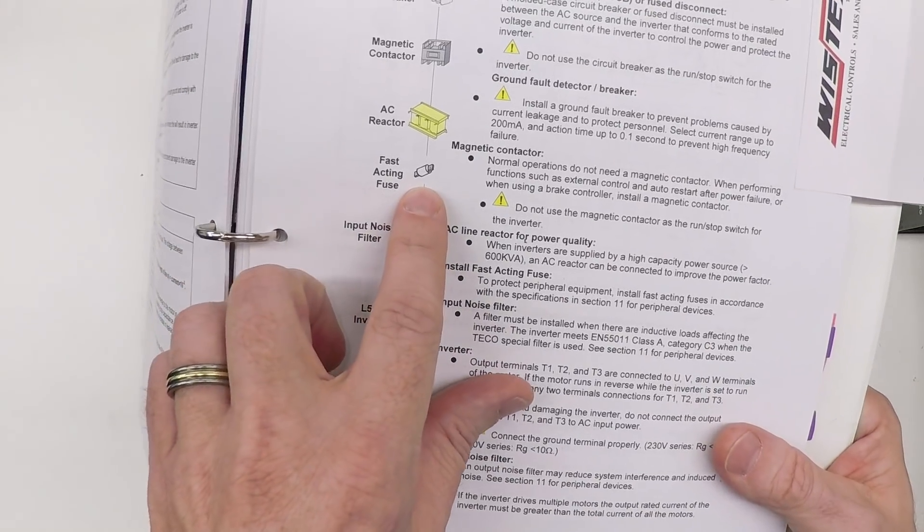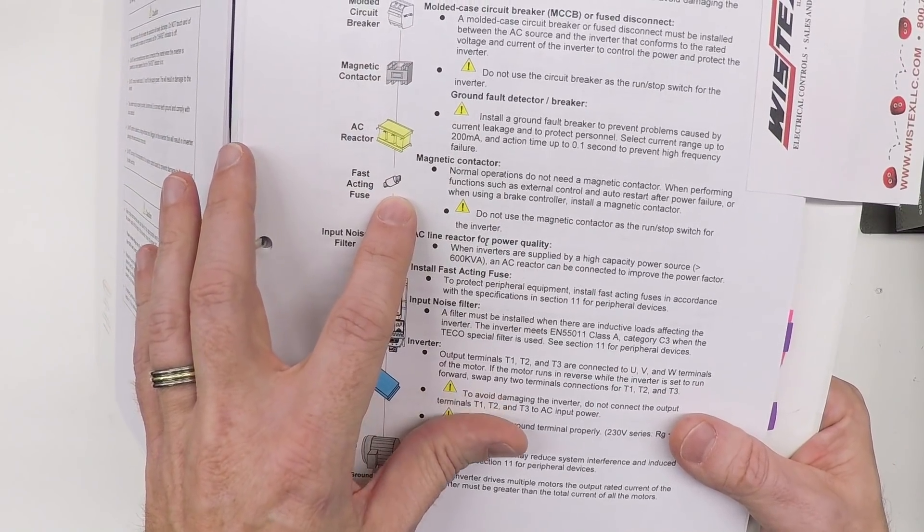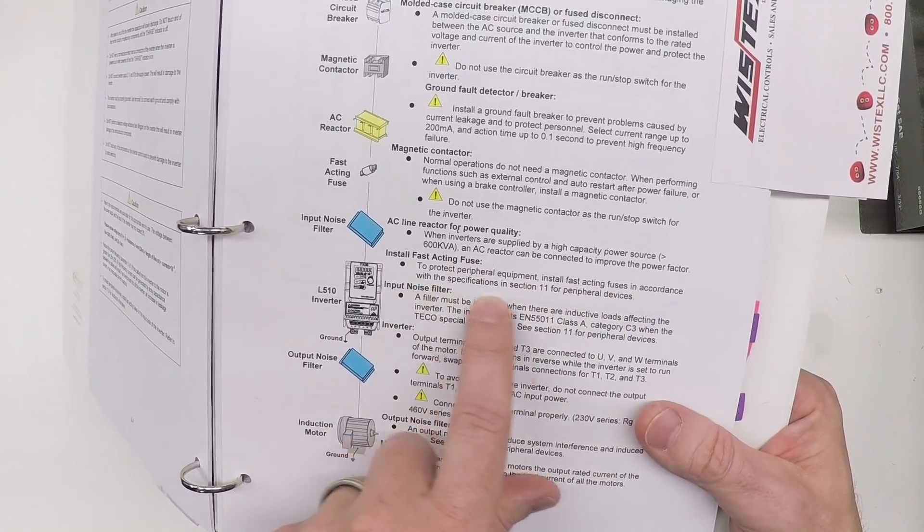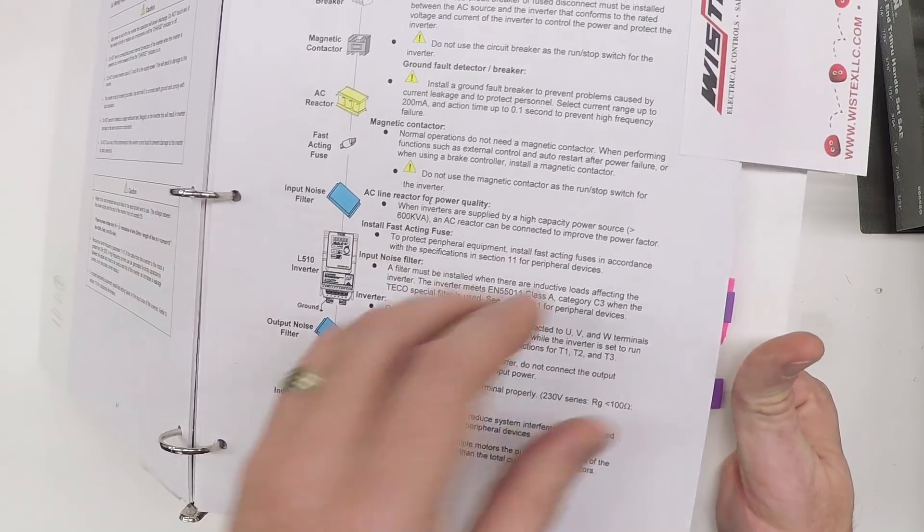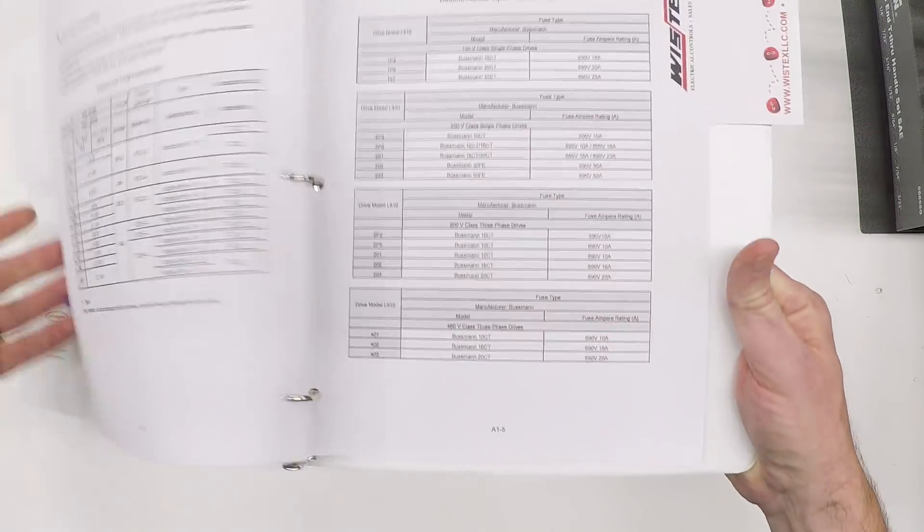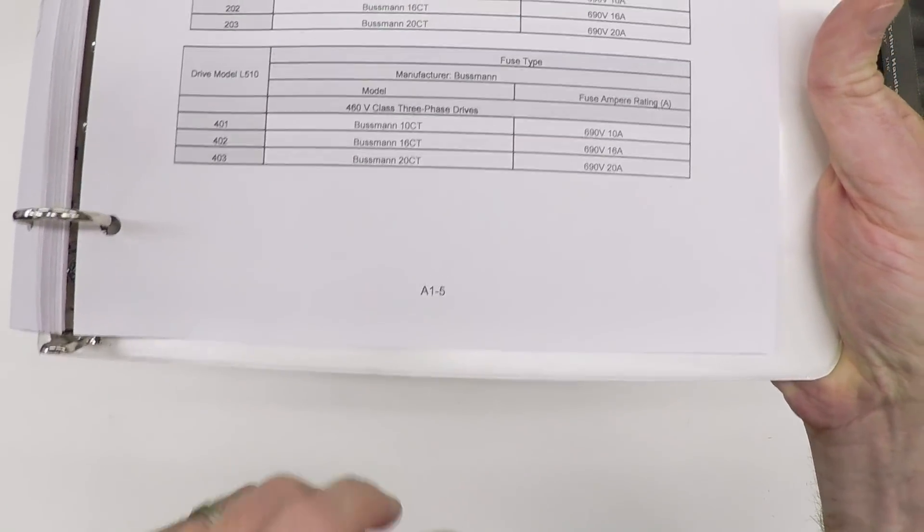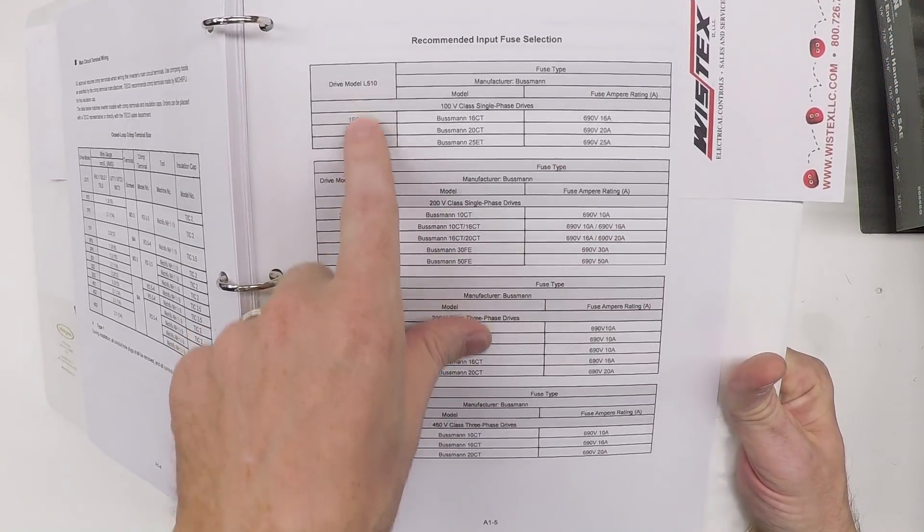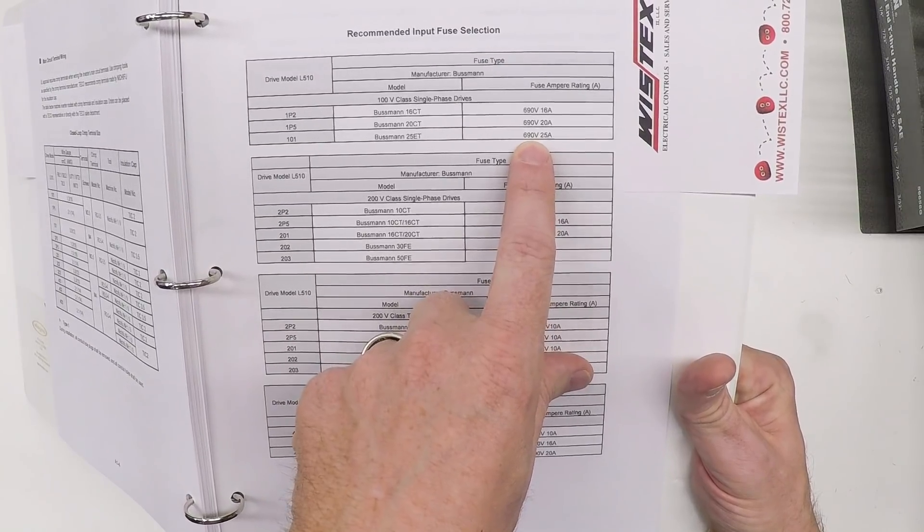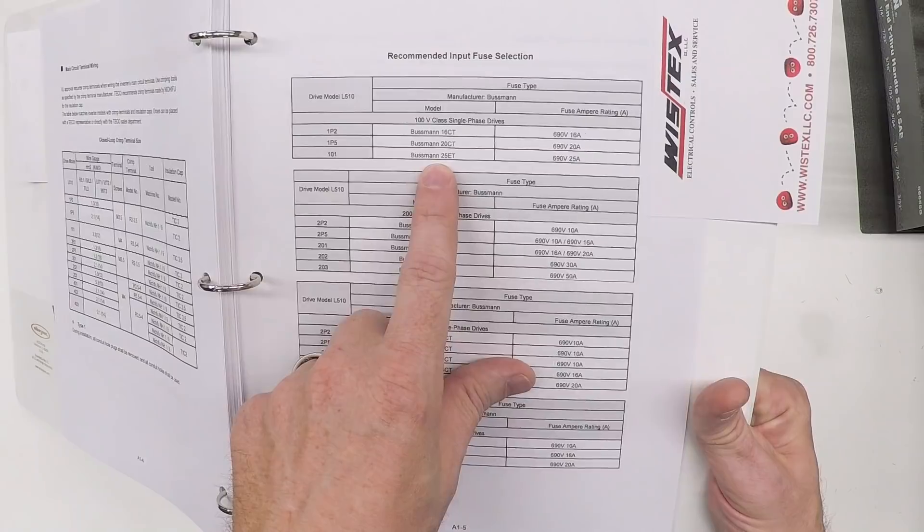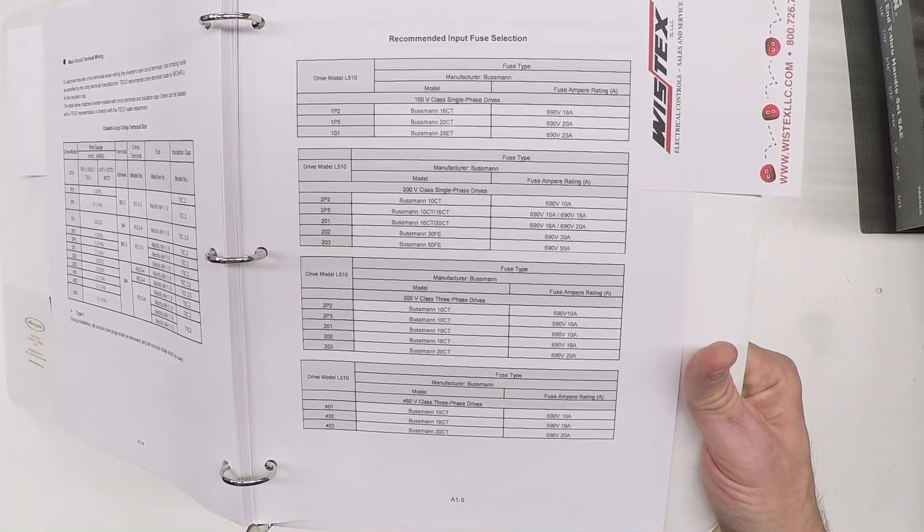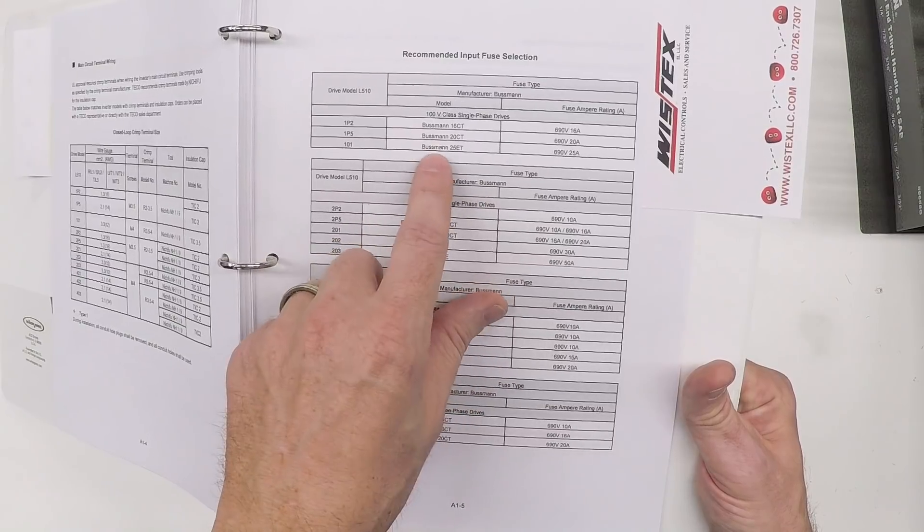Now, let's talk about this fast acting fuse. If you already have a circuit breaker, why do you need a fuse? Well, what it says here is to protect peripheral equipment, install fast acting fuses in accordance with the specifications in section 11. Now, this manual has no section 11, but there's one clue: fast acting. And if you actually dig here in the back, you'll find it not in section 11, but in section A1, page five, they have the spec. This is the L510 101 and they want a Bussmann 25ET, which is a 690 volt fuse, 25 amps. I went and looked at these and this is a British standard two stud mount fuse, which is really inconvenient for the things I can get locally and the mounting I have in the box here. So I found an equivalent fuse.